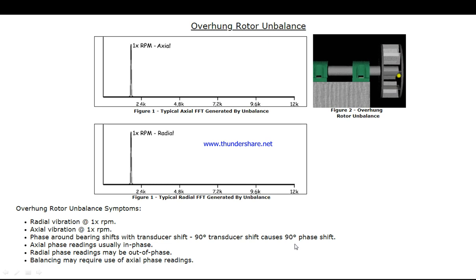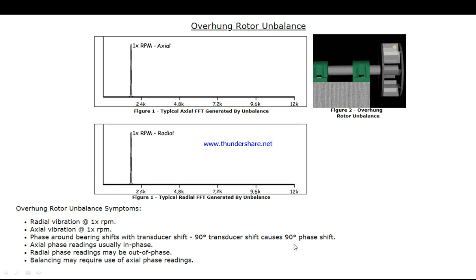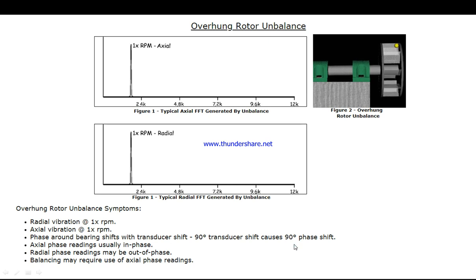Radial vibration at 1x RPM, axial vibration at 1x RPM, phase around with transducer is always 90 degrees. Axial phase readings are usually in phase, radial phase readings may be out of phase, and balancing may require use of axial phase readings.